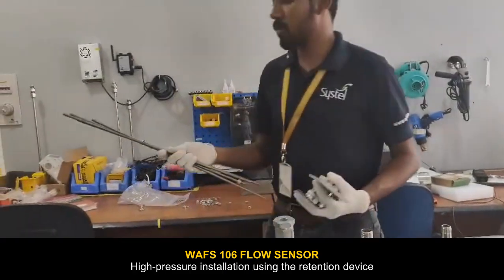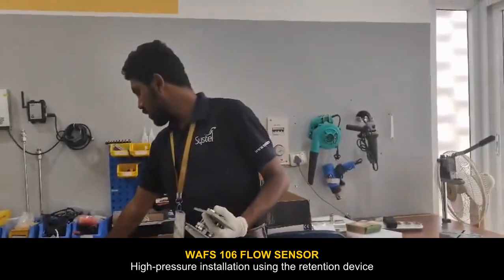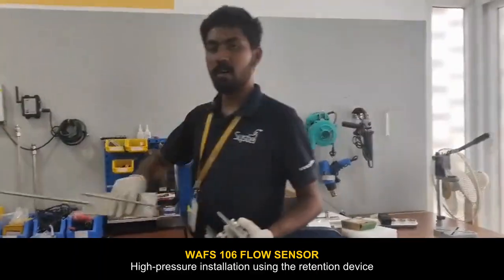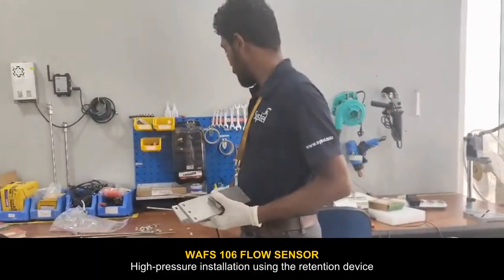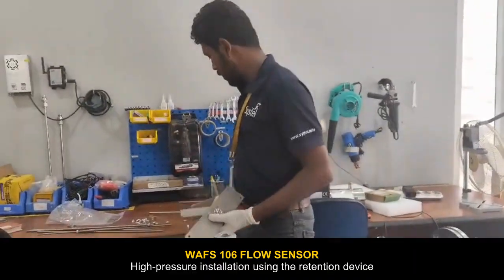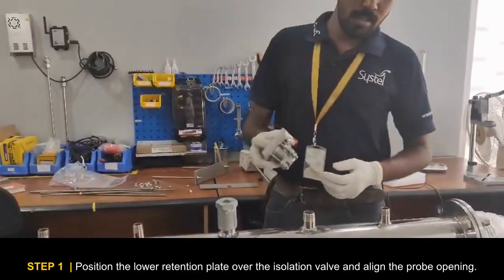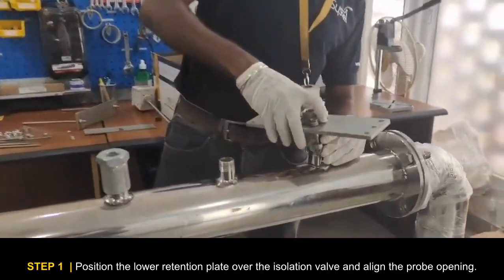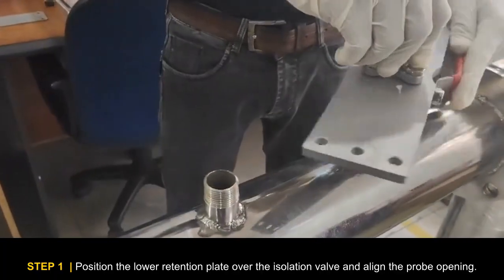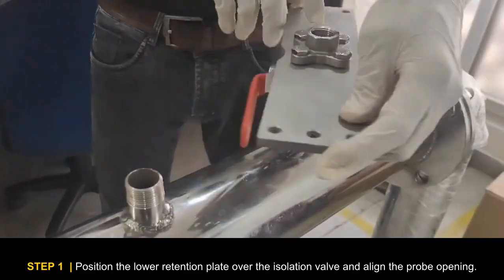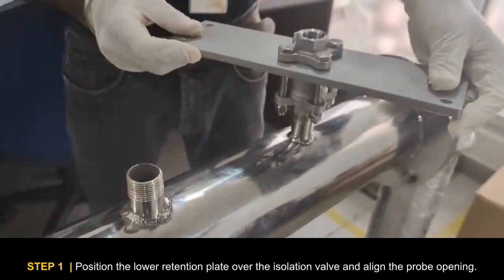This video demonstrates the installation of the WAFS 106 flow sensor in a high-pressure line using the retention device. Begin by positioning the lower retention plate over the isolation valve. Align the plate opening accurately with the valve and the probe entry point.